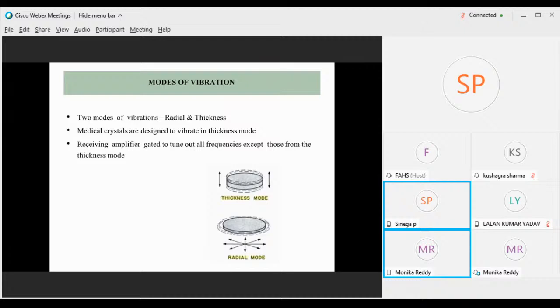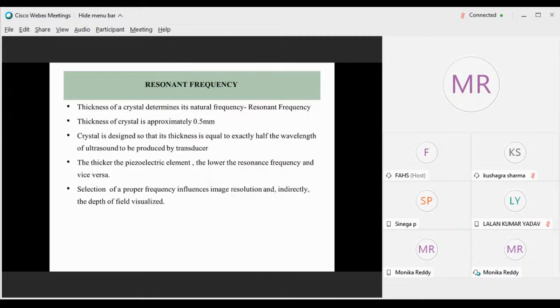There are modes of vibration for a transducer. There are two modes of vibration: one is radial and the other is thickness mode. Usual medical crystals use the thickness mode of vibration. We'll use only the thickness mode, and the receiving amplifier will tune out all the frequencies except those from the thickness mode. In the receiving amplifier, if the signals are from the thickness mode, we'll get them, or otherwise we won't.